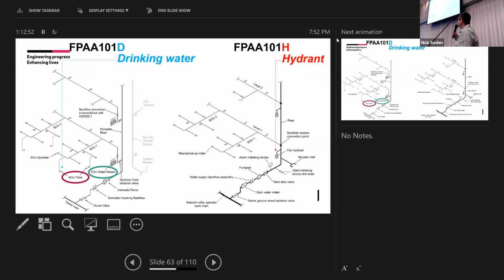So I think, is there any recommendation regarding the backflow prevention, especially the stagnant water in the fire sprinklers in the domestic water system? Yeah, so that's probably the biggest contentious chat about this at the moment. It only requires a standard backflow prevention device. It's not a monitored, it's not an RPZ valve, and that's where some states are still fence sitting to see if it's going to change in time. Because we're talking about a system of fire and a system of residential sprinkler, a residential hot and cold water. How are they mixing? How are you holding that away? So look, I feel that may change in time. However, at the moment, it's just a standard backflow prevention device.